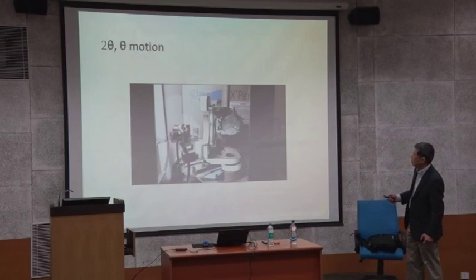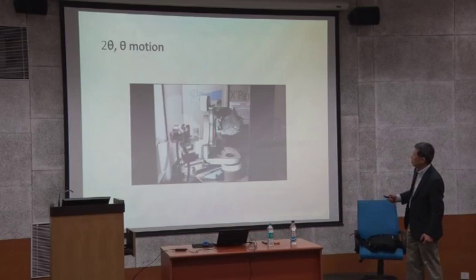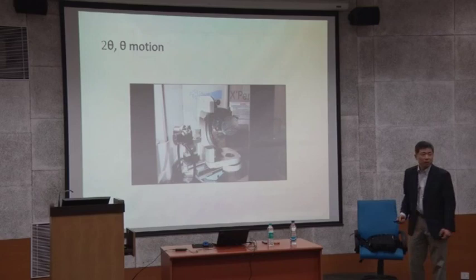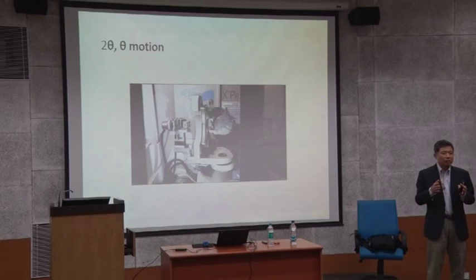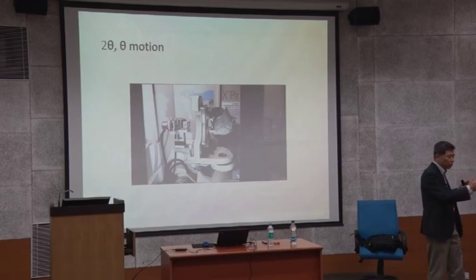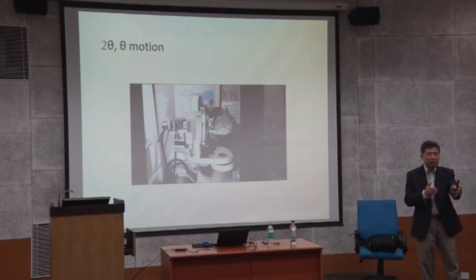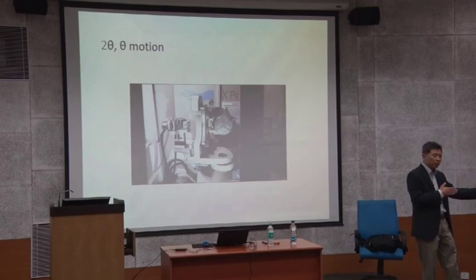The theta motion and two-theta motion can go independently. Most of the time with the diffractometer, you don't really use independent motion — it's continuous coupled motion. We call this the coupled scan. Which means theta is always half of the two-theta value. Both starting from zero: theta moves this much, and two-theta moves twice as fast. That is the Bragg condition — we call it the bisecting condition. Bisecting means divide by half.